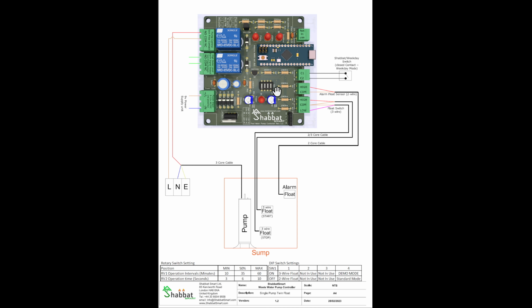Then we have 4 dip switches, where dip switch number 1, right over here, dictates low or high, which means a 2-wire float or a 3-wire float. In our case, for this setup, it has to be set to 1 for a 3-wire float. Dip switch 4, this one over here, dictates standard mode or demo. Demo mode is commissioning mode.